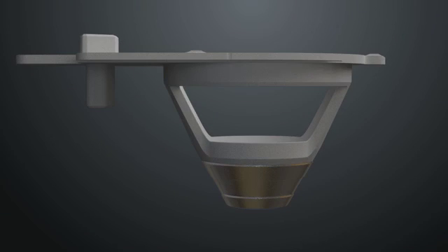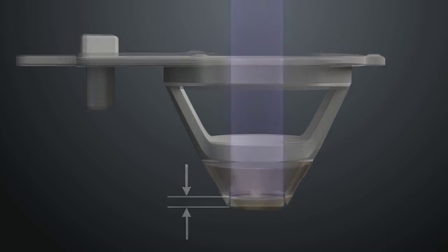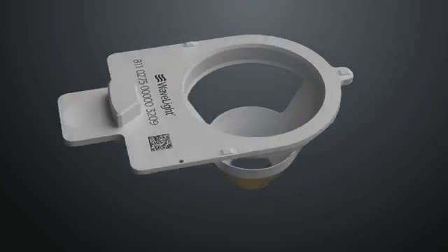The WaveLight FS200 uses a ballast control check to automatically calibrate each applanation cone, adjusting for the thickness of the glass and temperature shifts within the laser system's components. The calibration process provides consistent and predictable flap thickness.